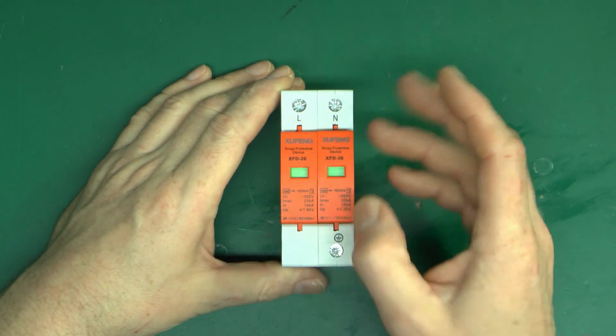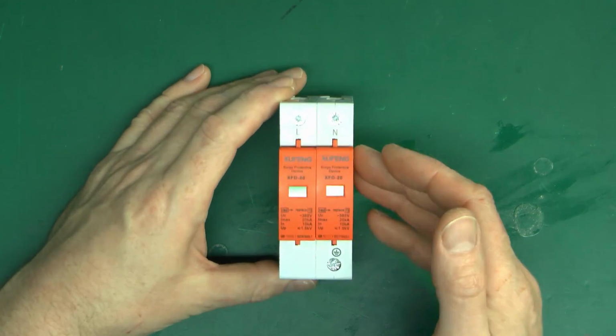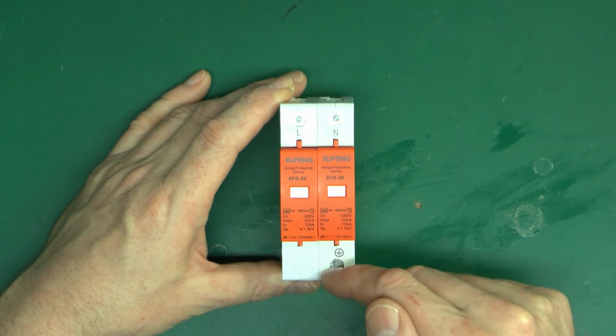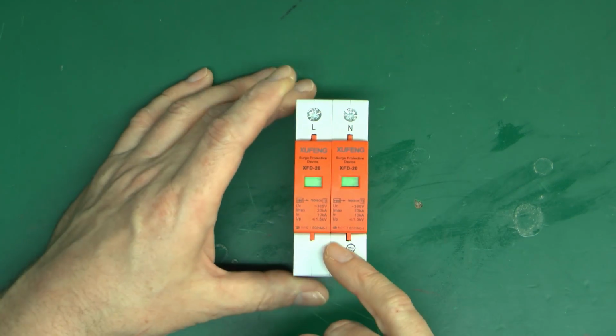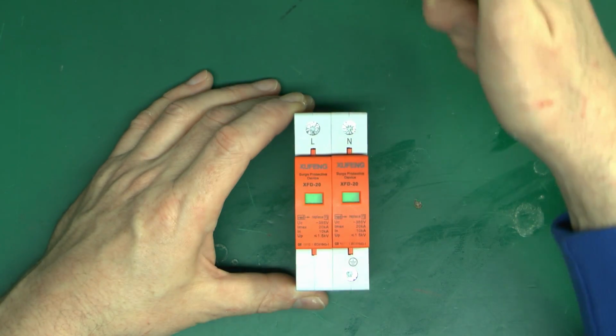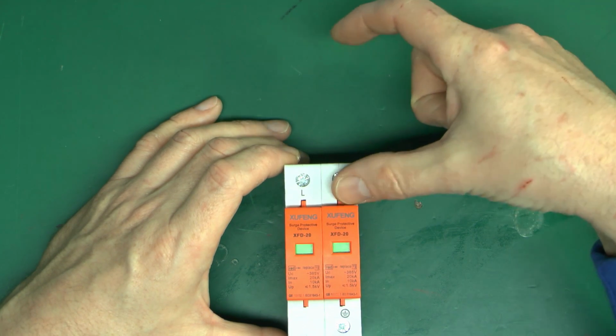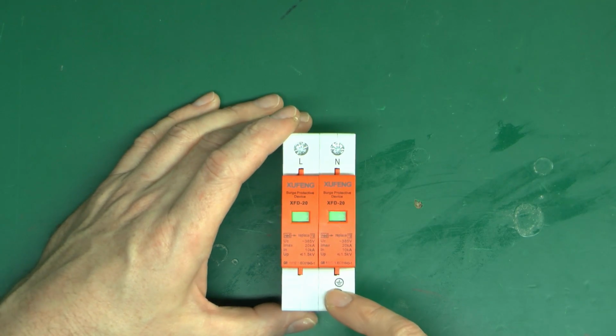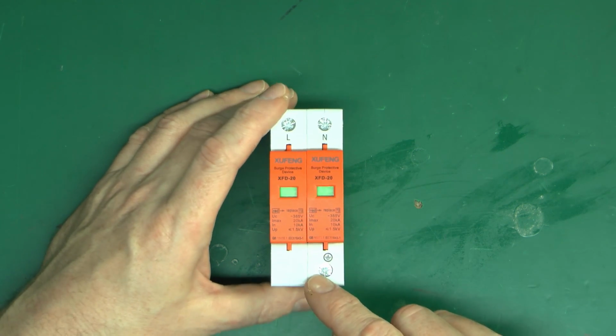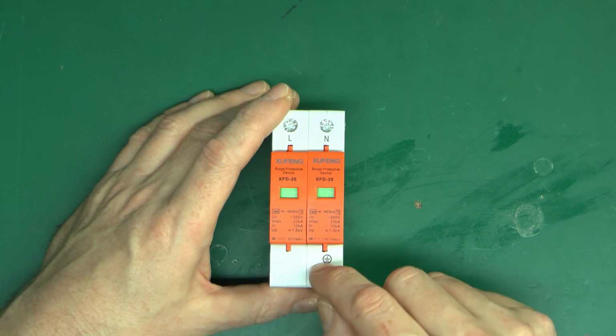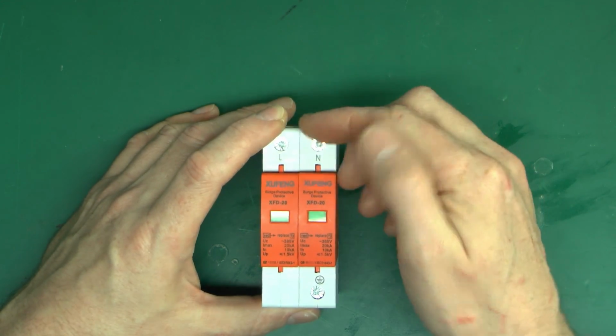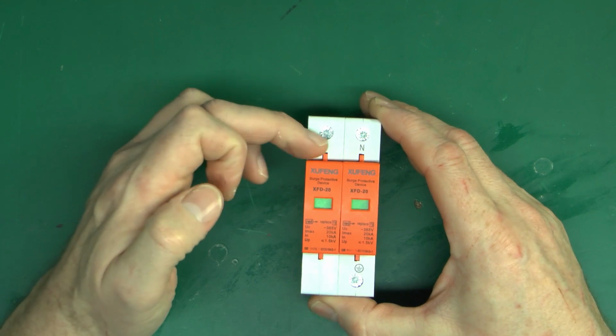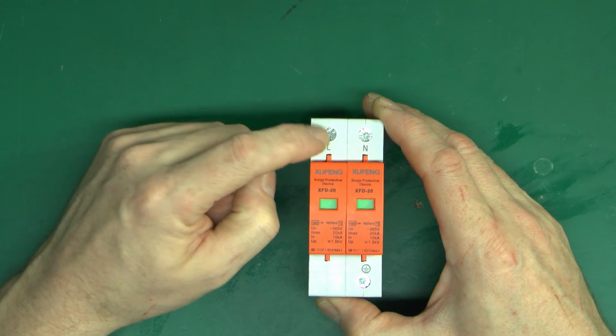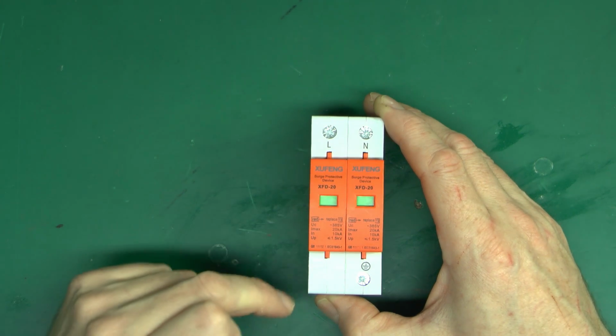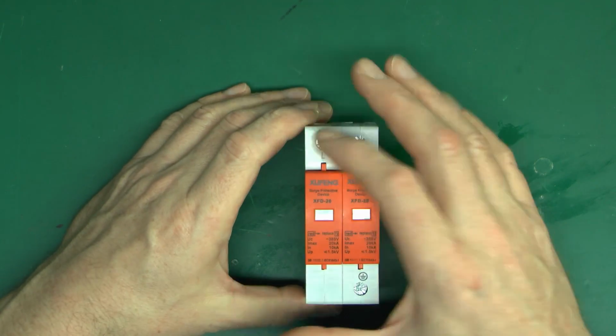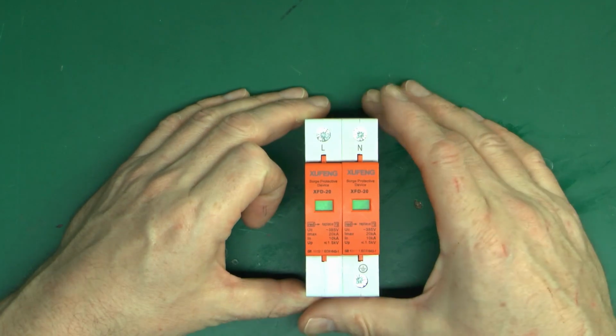And if you've got a type like this, which will go in your typical consumer unit, the distances are the length of wires between these terminals and the terminals in the consumer unit. So in case of the neutral, that just goes from here to the neutral bar. So you want to make that again as short as possible, generally only a few centimetres there. Again, the earth, you want to make that as short as possible, although it's nice to put these in a nice tidy way and sort of route it around the outside of the box. In this particular case, it's better to take it simply directly from here straight to the earth bar, again making that as short as possible. And the line one, if you have a separate circuit breaker there, it's essentially the distance from here to the circuit breaker, and then also the distance from the circuit breaker back to the main switch. So again, it's just generally a small loop on the top, just a few centimetres in length.